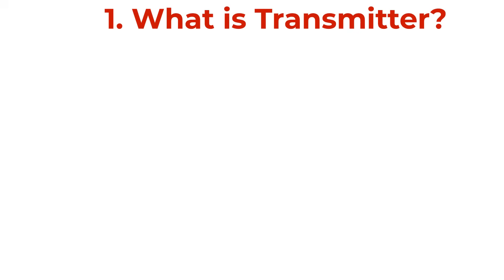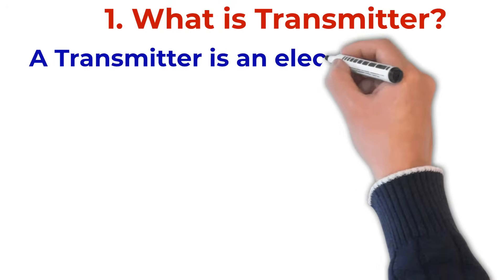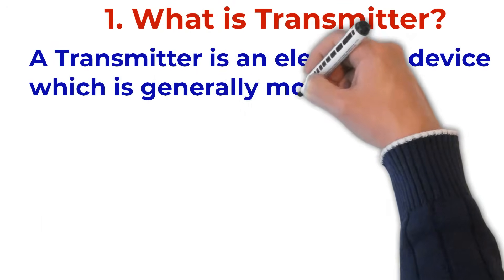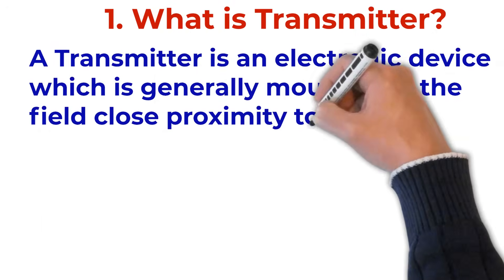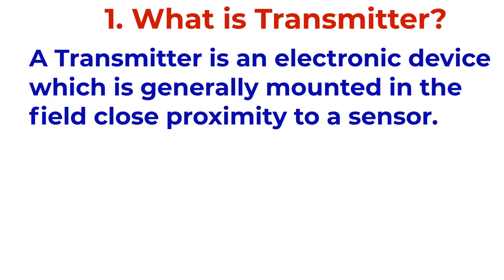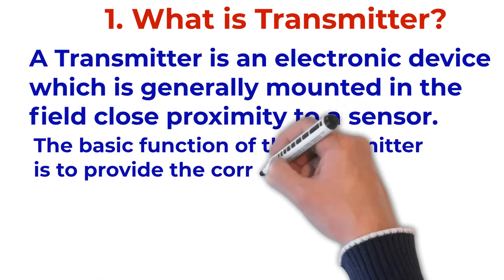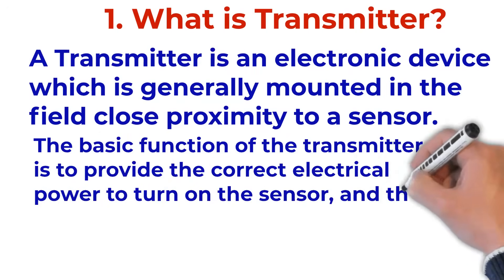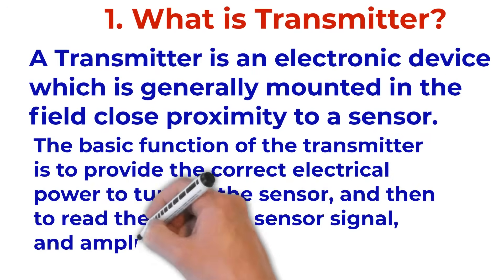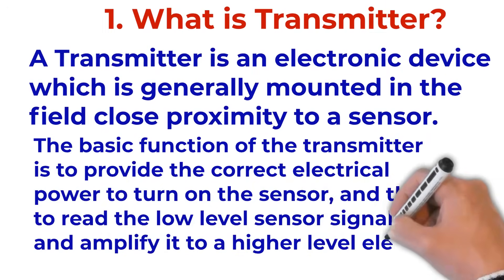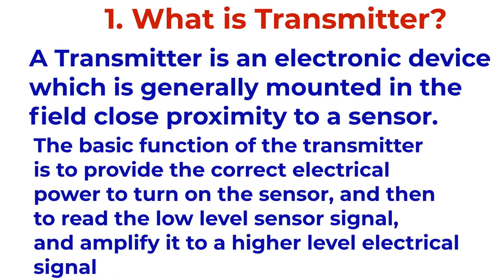You need to give a short definition of a transmitter. A transmitter is an electronic device which is generally mounted in the field and is in close proximity to a sensor. The basic function of the transmitter is to provide the correct electrical power to turn on the sensor, read the low-level sensor signal, amplify it to a higher-level electrical signal, and send that signal a long distance to a controller or readout device.